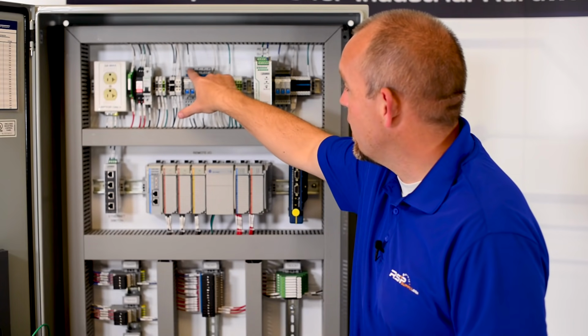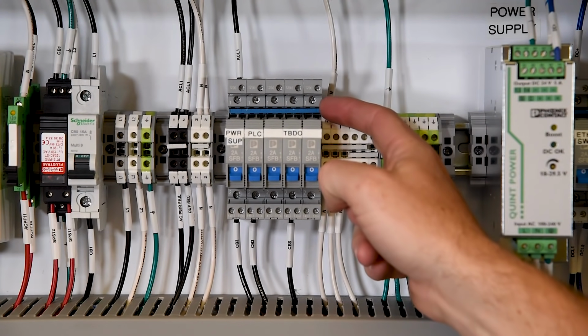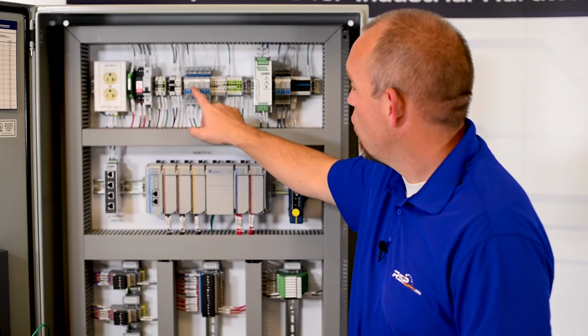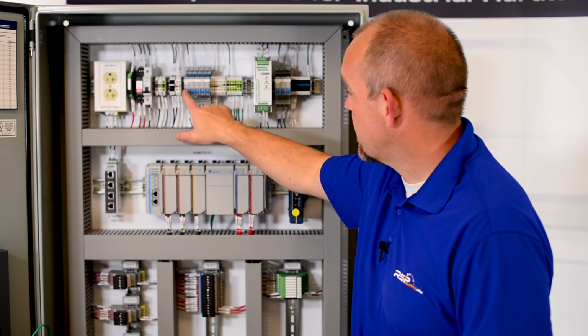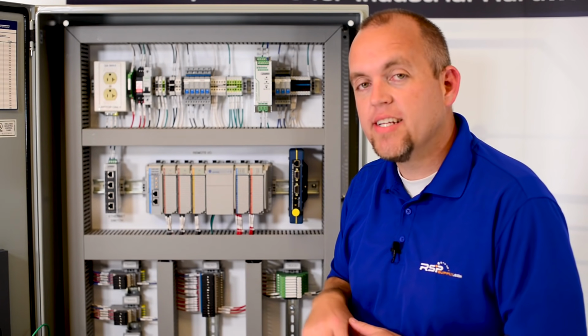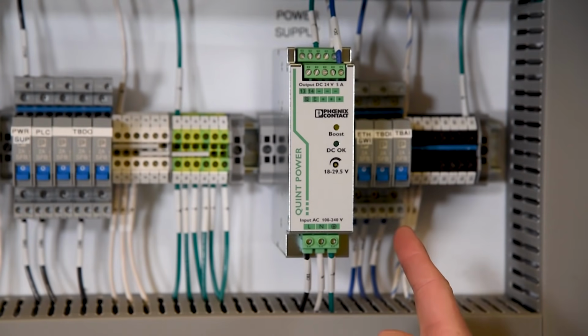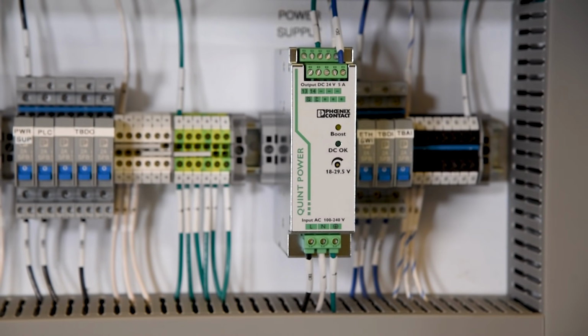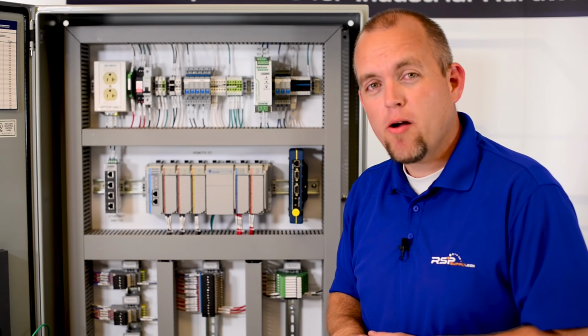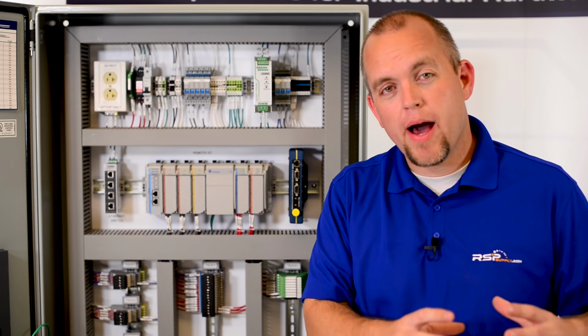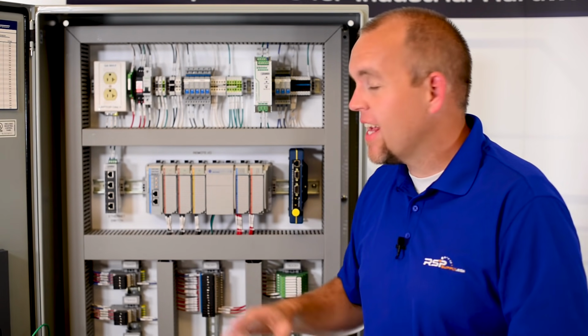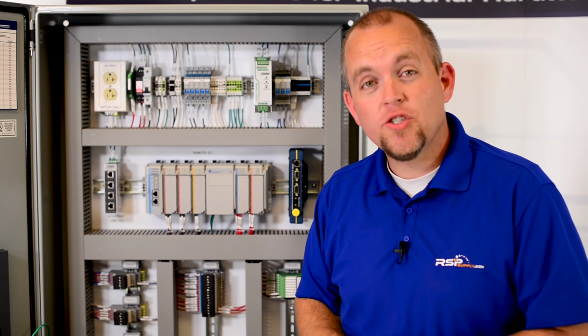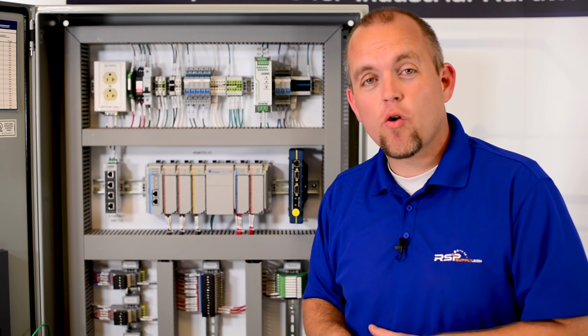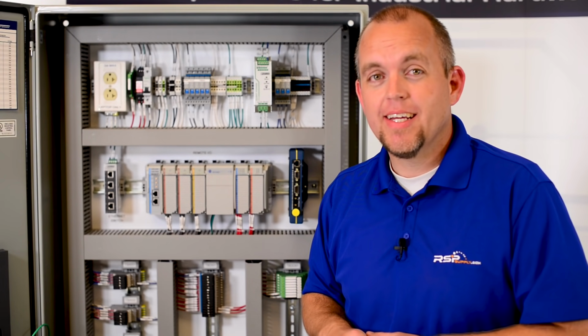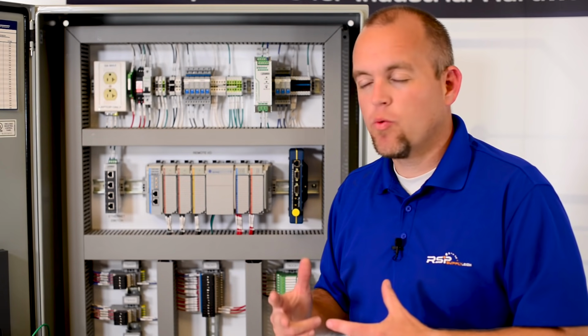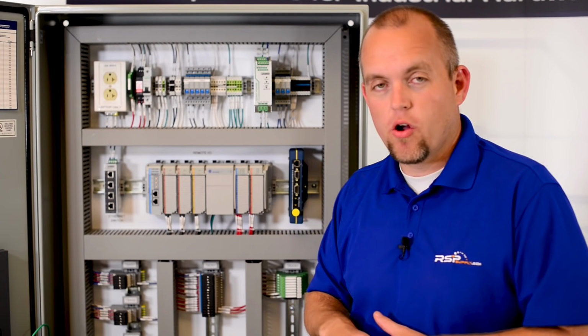We have one wire coming in and it connects all these circuit breakers with this jumper bar here. We then send power, AC power in this case, to the components that require AC power within this panel. One component that requires AC power is our power supply. Now the power supply's function is to change one type of power to another type of power. In this case, the power supply takes 120 AC voltage and converts that to 24 volts DC voltage, which is the voltage that's required for the majority of the components within our control panel.